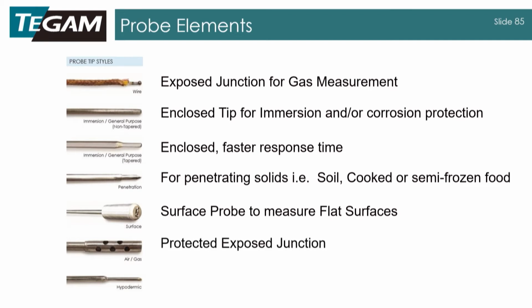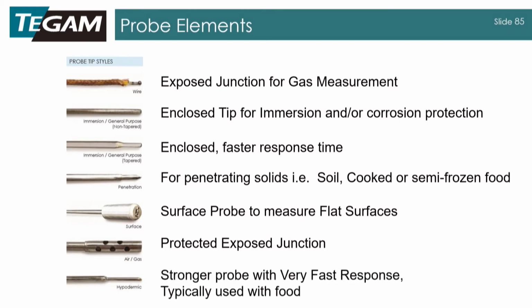This next one is an exposed junction, but it has kind of like a grill over it, and basically that's to just protect it from contaminants, you know, high winds, things like that. And then lastly, you have a hypodermic probe. Works very much like the tapered and the immersion, also used with food, and it's got a very fast response just because smaller surface area, faster response time.